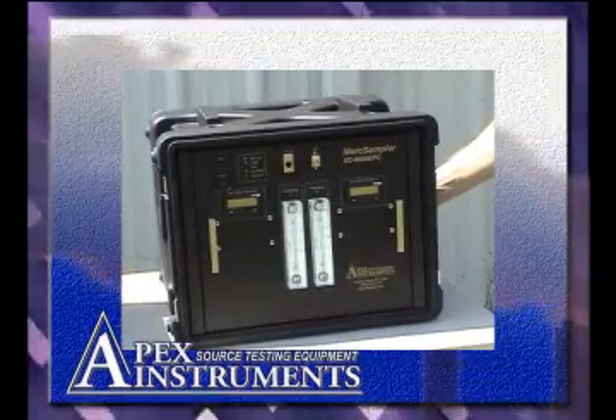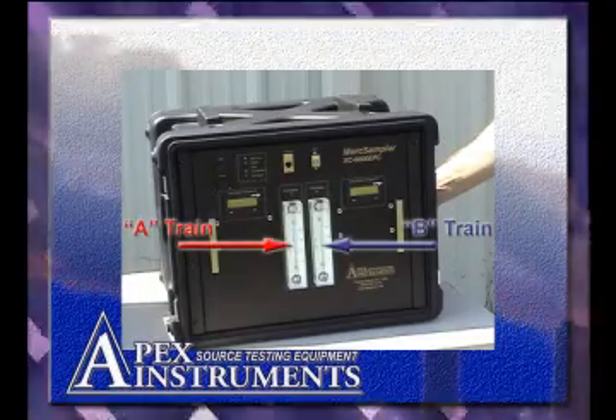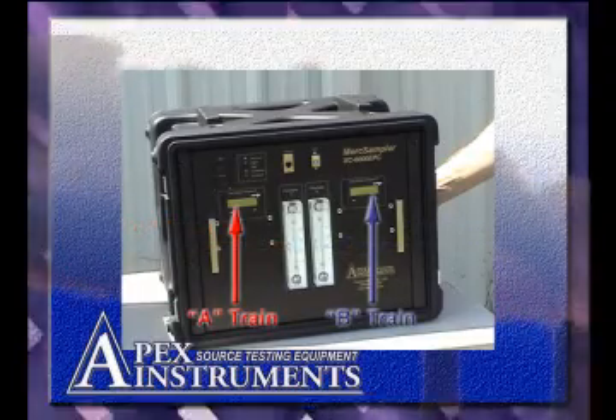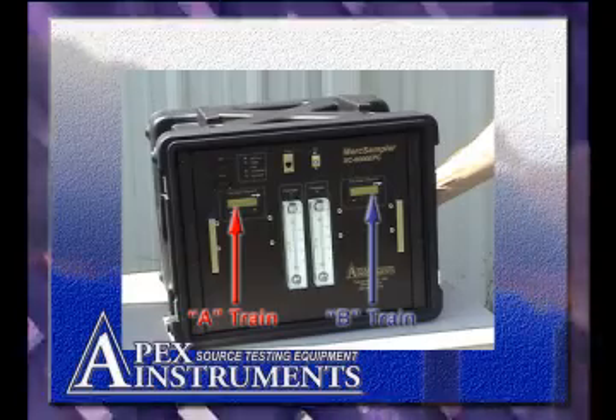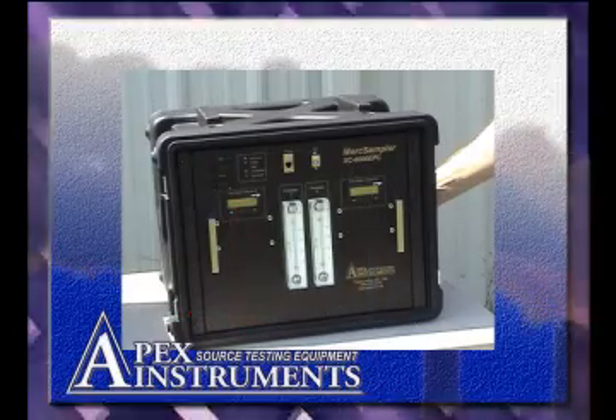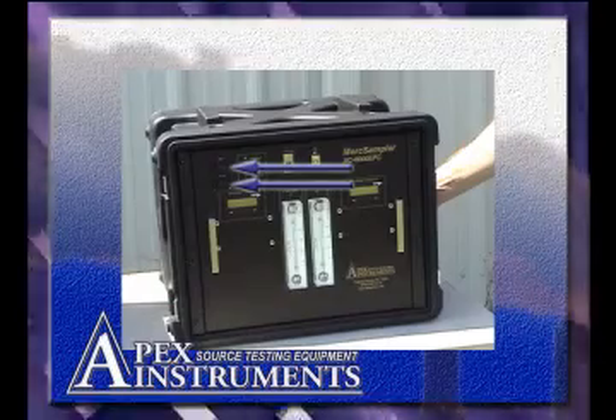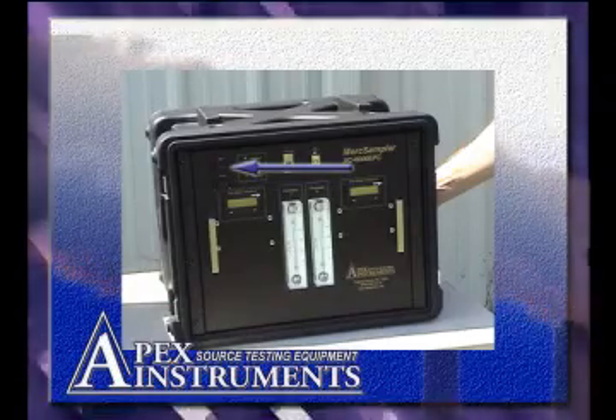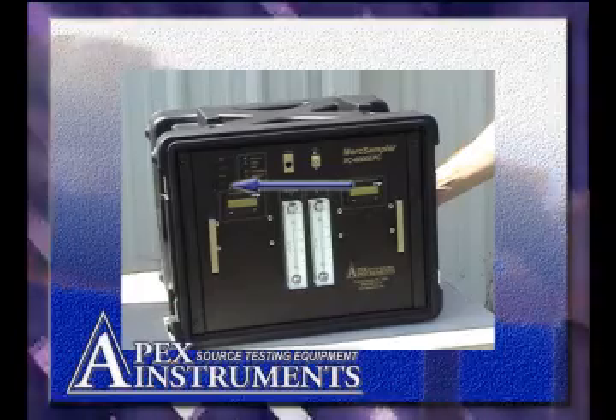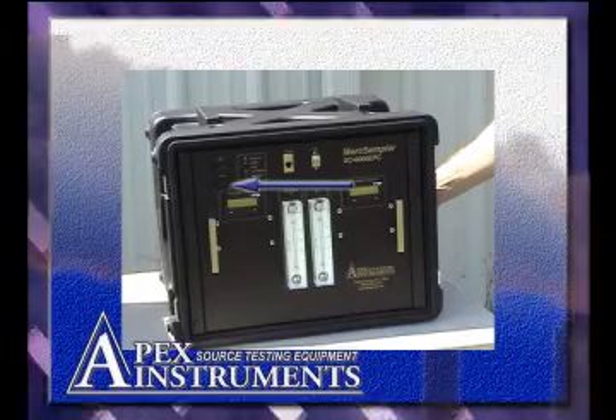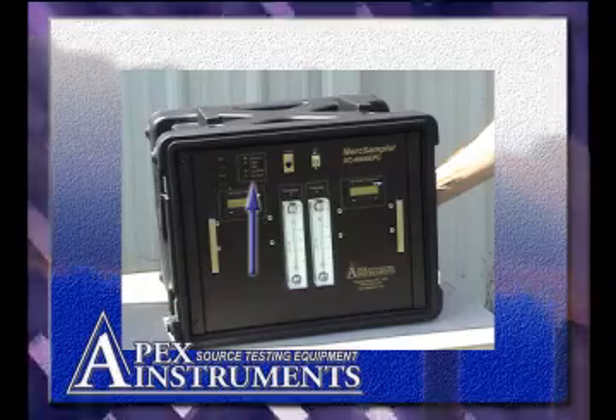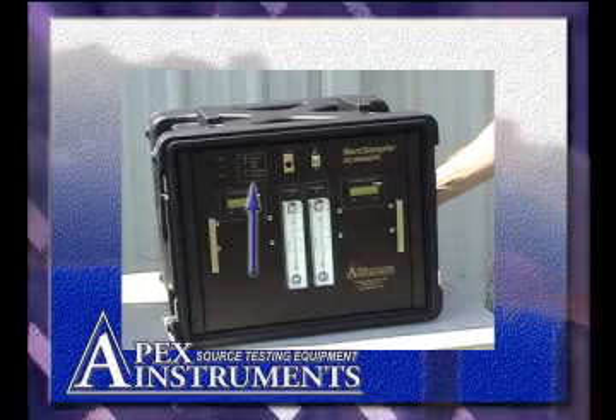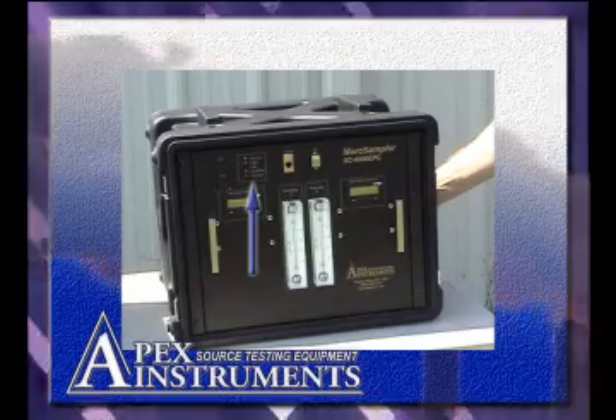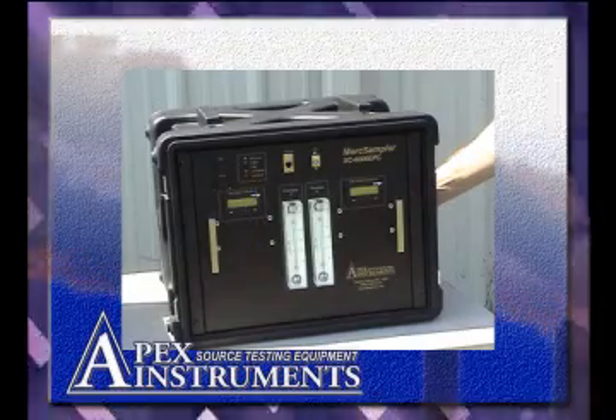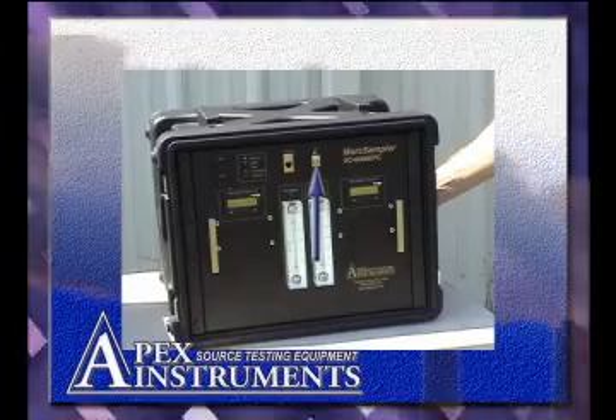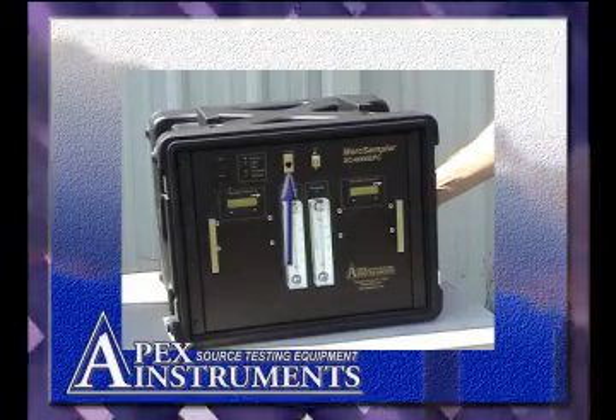With the front of the console open, the operator will find the rotometers and dry gas meter LCD digital displays for the A and B sample trains. There are two power switches, one to power the XC-6000 console and one to provide probe heater power. Opposite the power switches, there are LEDs for operation status and alarm notification purposes. Direct PC interface is possible through the front panel USB or Ethernet connectors.